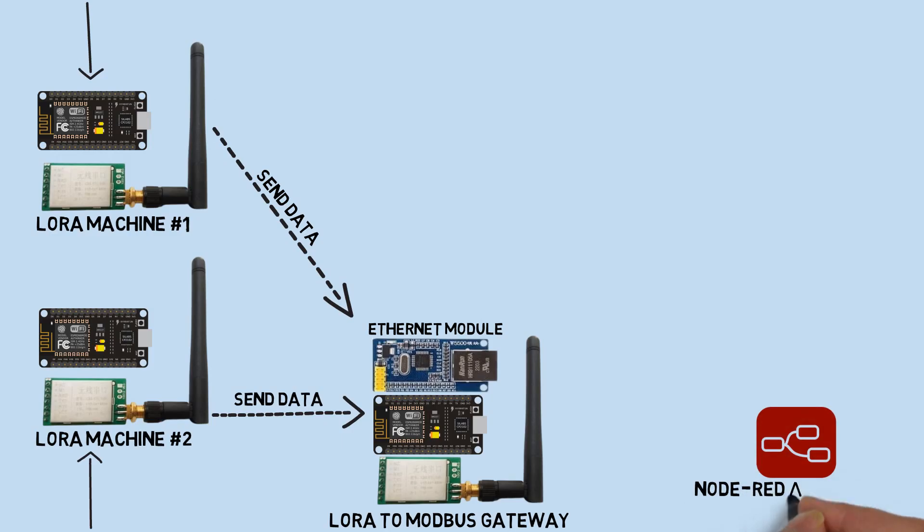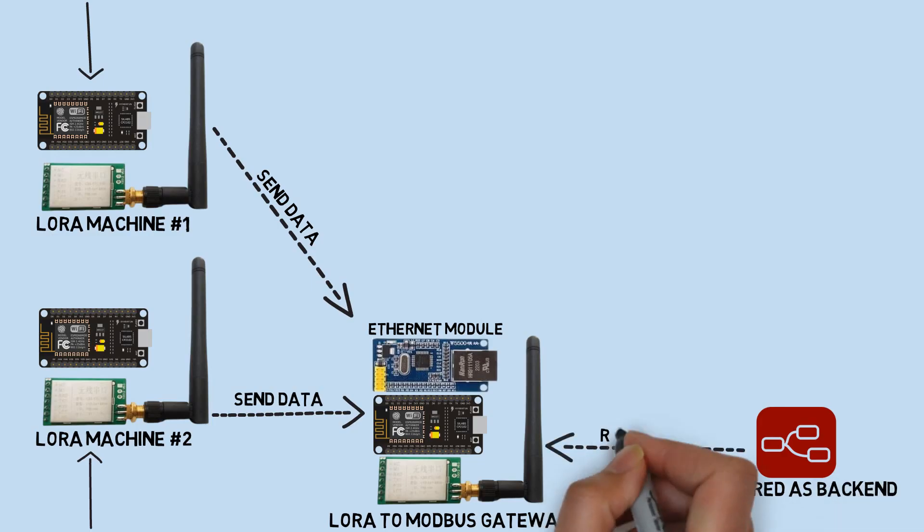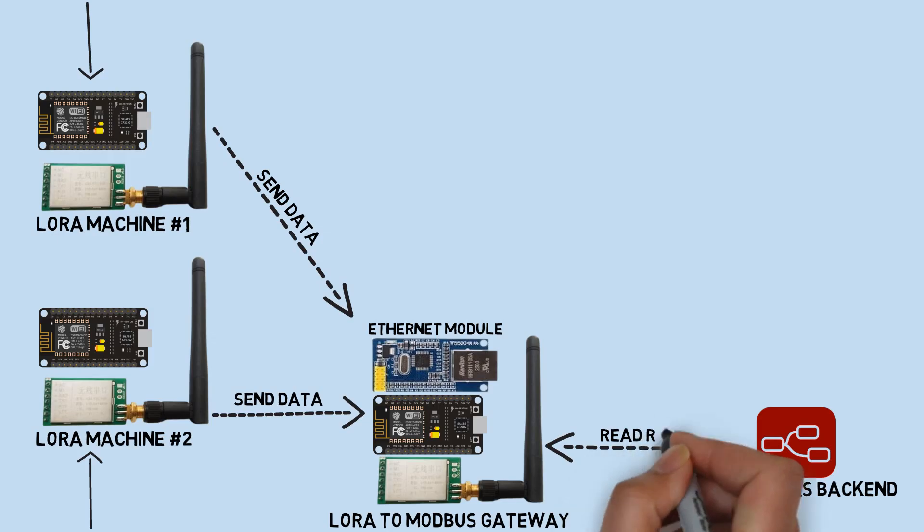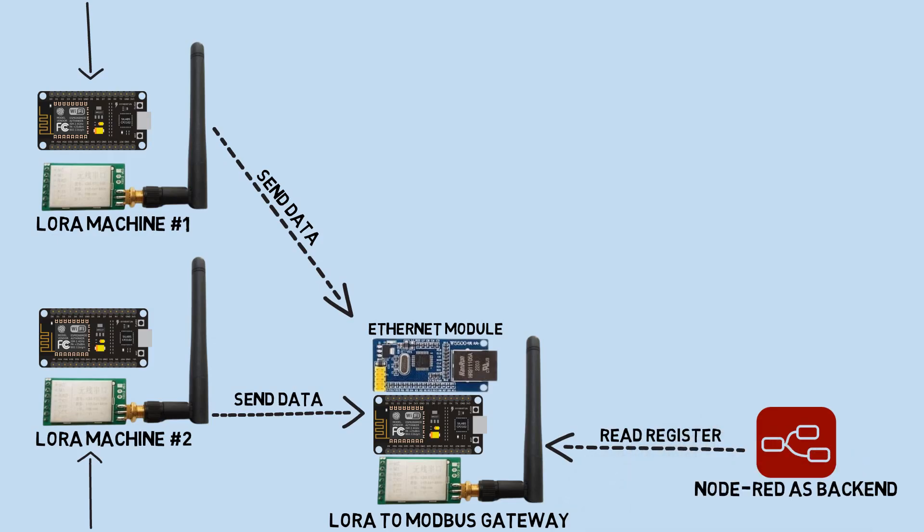Node-RED installed on the computer will connect to Modbus as a Modbus client and read the registers. The changes in the register values will then trigger queries to store the data in a PostgreSQL database.